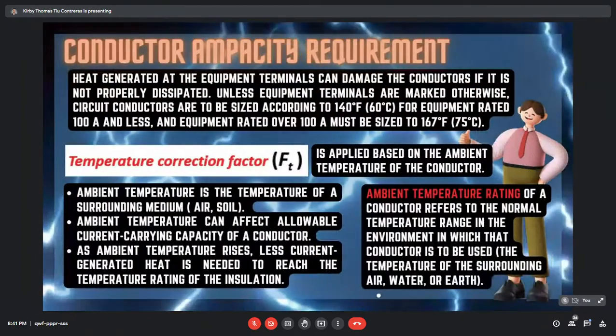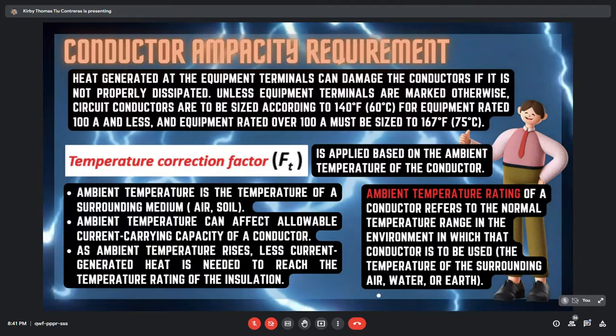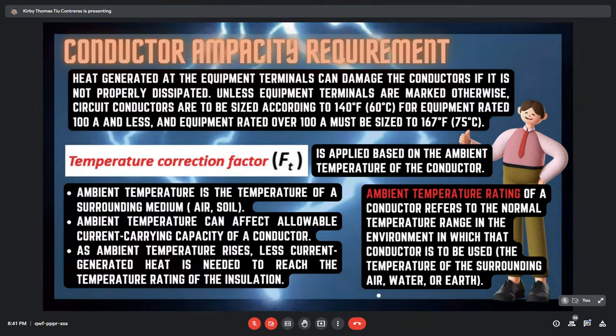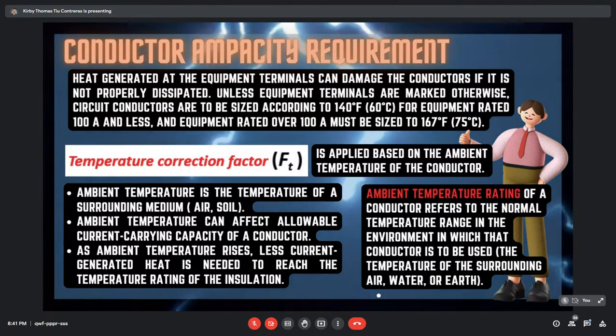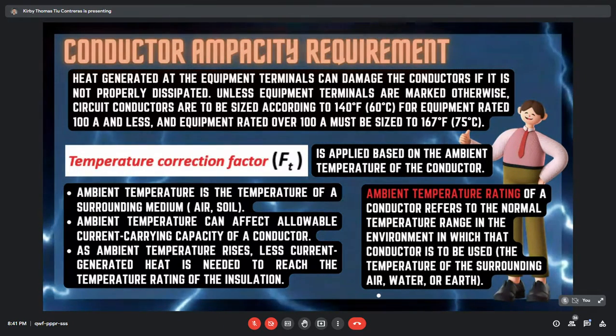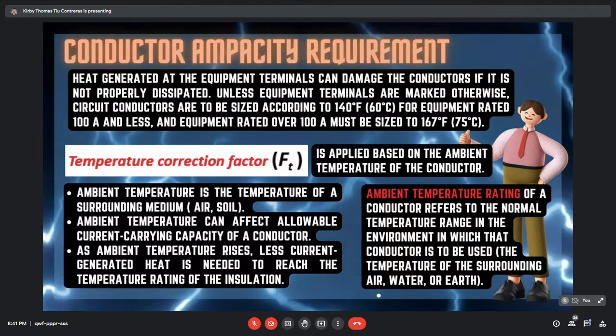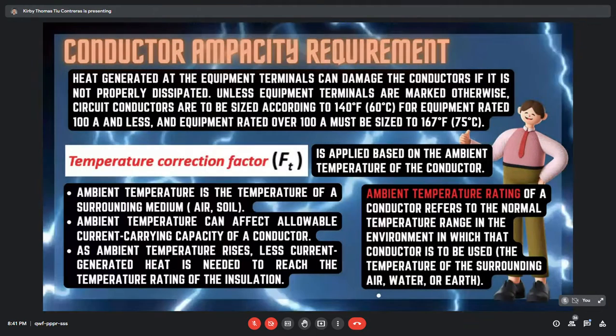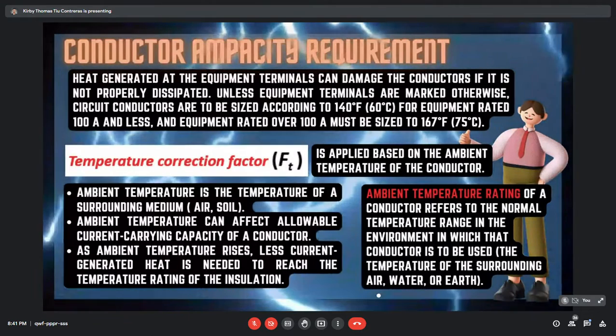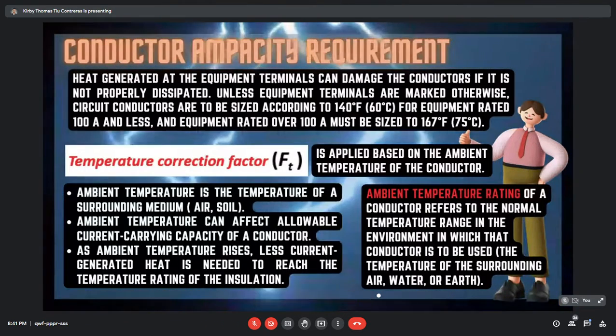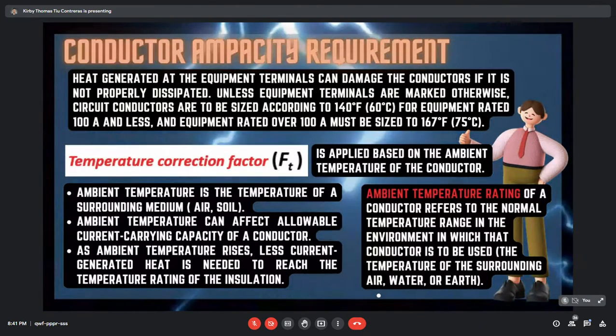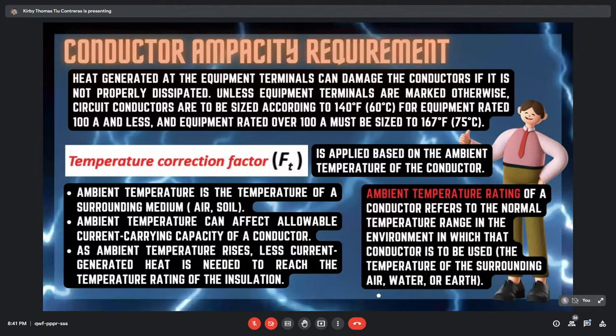Conductor ampacity requirement. Heat generated at the equipment terminals can damage the conductors if it is not properly dissipated. Unless equipment terminals are marked otherwise, circuit conductors are to be sized according to the 140 degrees Fahrenheit, or equivalent to 60 degrees Celsius, for equipment rated 100 amps and less. And equipment rated over 100 amps must be sized to 167 degrees Fahrenheit, or equivalent to 75 degrees Celsius.